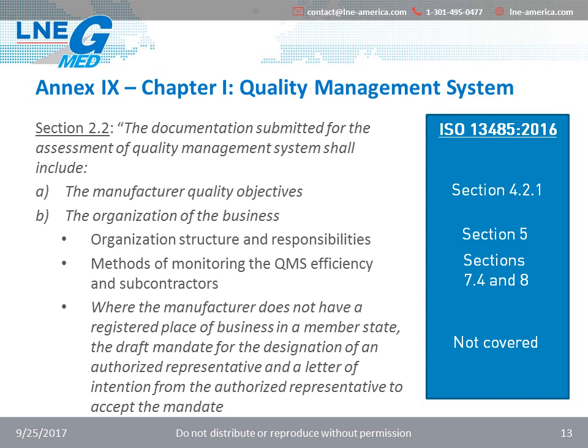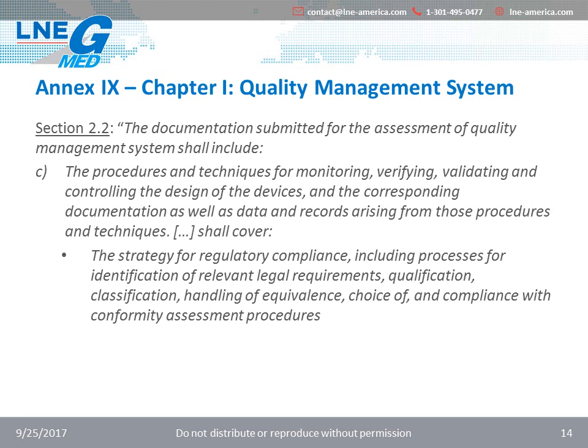So here again, if you're established outside the European Union, be careful to have all the processes, and in this case the documentation. These two pieces of documentation are clearly stated in the document that you will submit to show the assessment of the quality management system following Annex 9 of the regulation. Another set of documents that you have to provide is the procedures and techniques for monitoring, verifying, validating, and controlling the design of the device, as well as all the corresponding documentation and data, records, and everything linked to the implementation of these procedures and techniques. And this specifically should cover the strategy for regulatory compliance, including processes for identification of legal requirements and all other elements. This section is not covered in ISO 13485:2016.